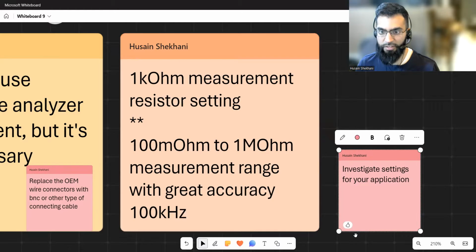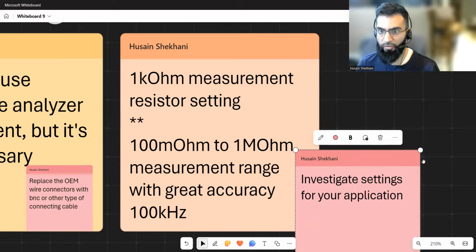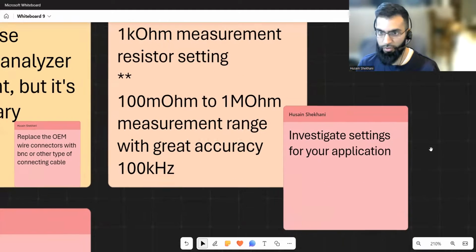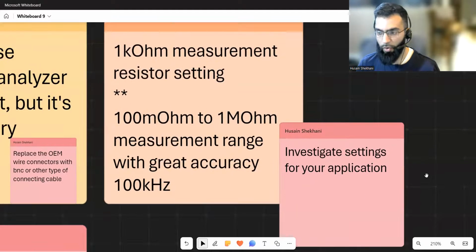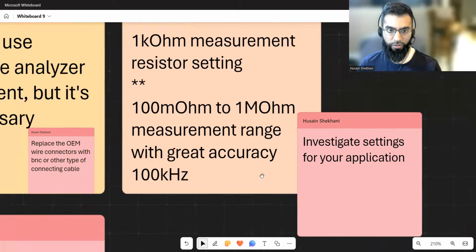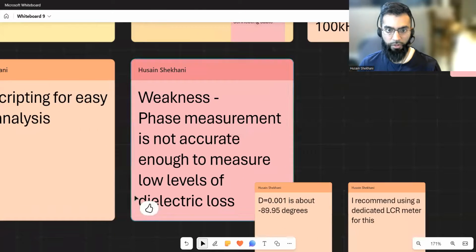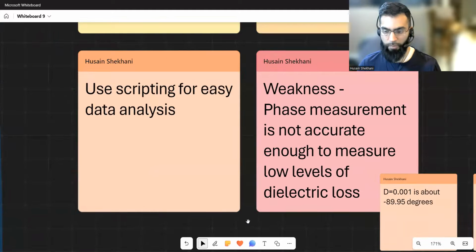Just investigate the settings for your application. How do you investigate that? You use resistors to check, say you have a device at 5 ohms at 1 megahertz, can you trust the measurement? You measure known resistor values with your system and see how accurate you can get, and what the open and short circuit impedance values are.